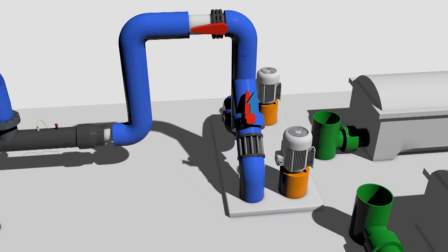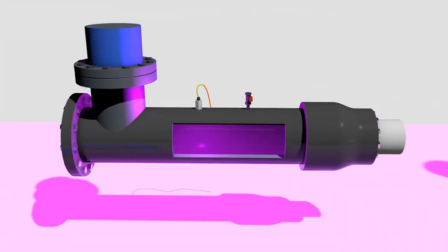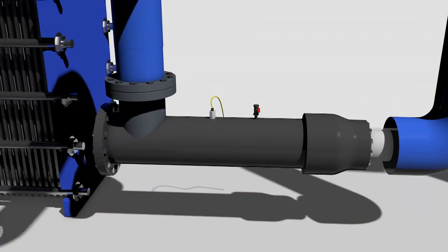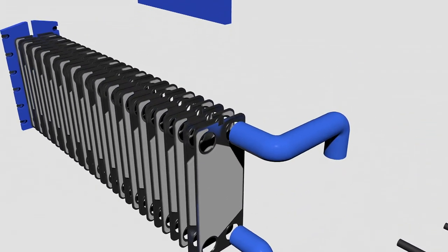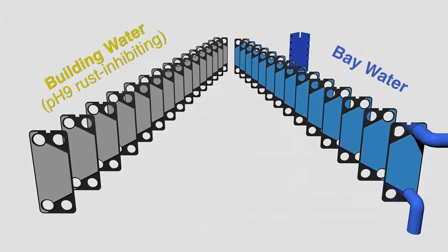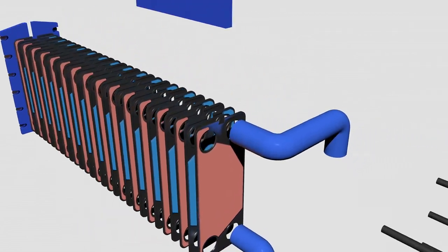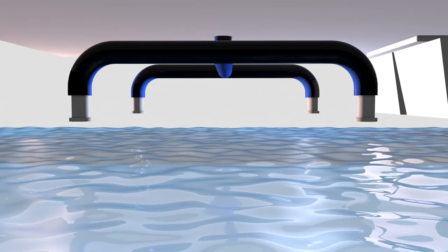It then pumps that salt water out of the tank through a UV sterilizer and then into a titanium plate heat exchanger. Fluid is placed on opposite sides of the titanium plates, with the salt water on the opposite wall of those plates. They come together but don't physically touch, and what you get is a temperature exchange between the two through the plate of titanium. After the bay water has come through and the heat exchangers have done their work, it is then returned to the bay.